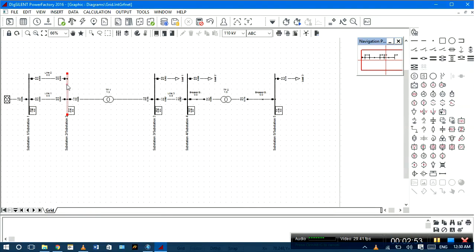a fault that is on this bus and on this bus, because those two faults are outside of the protected zone. The differential protection will look at the current that is flowing in that line and the current leaving that line going that side. It will not see a fault that is on this bus or on that bus.